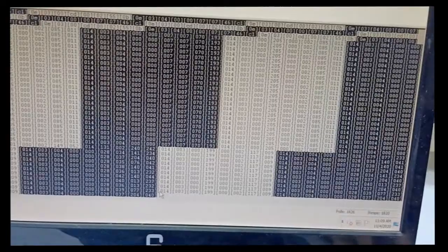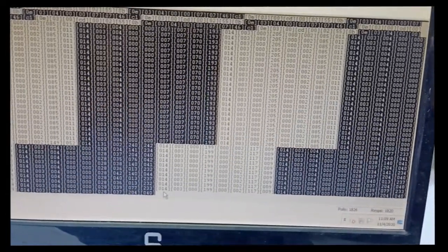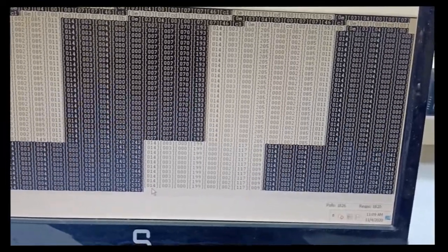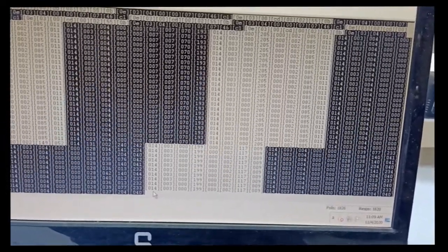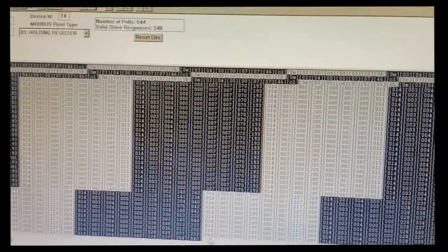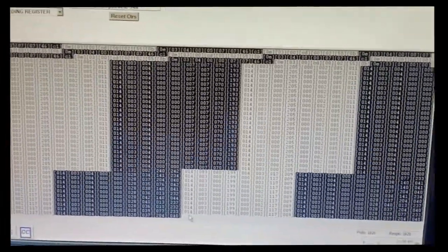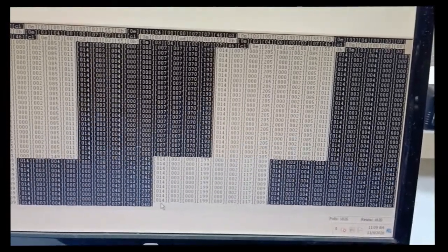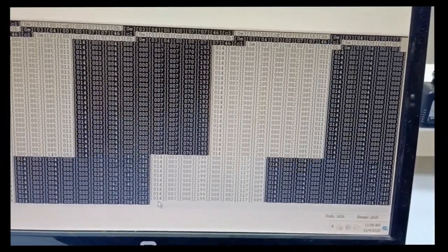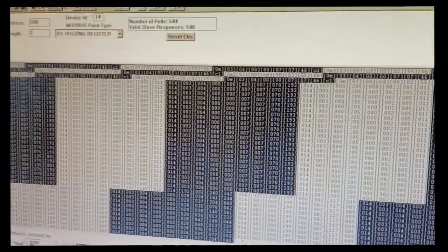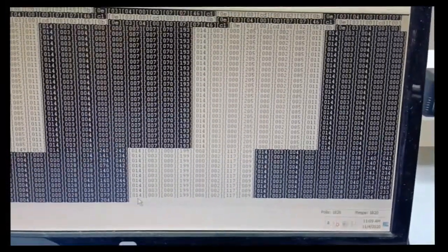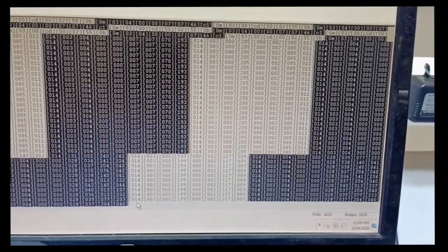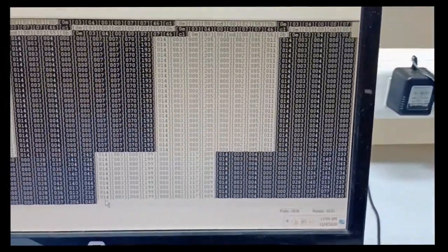The first byte is the meter station ID. Then the second byte is the query type. Then 2 bytes are the starting address for the parameter. Here we have fed address 200, but Modscan32 decrements that address by 1, so it is sending address 199 to the meter. Then we have asked for length 2, so the next 2 bytes are 0002. Then the last 2 bytes are the CRC.